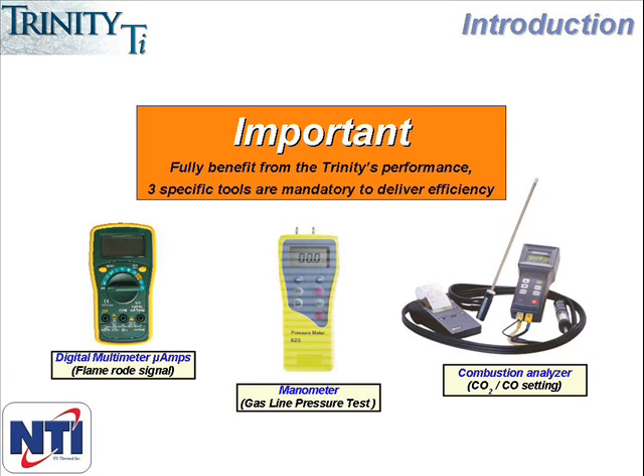as this is required in order to read the flame signal strength. You also need a manometer in order to measure gas line pressure, and a combustion analyzer to do a combustion analysis to ensure the gas valve is properly adjusted to the proper CO2 and CO levels.